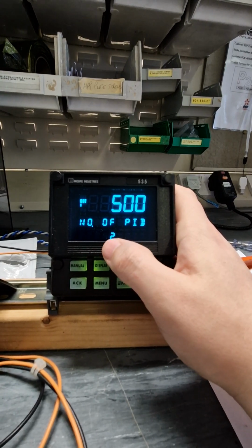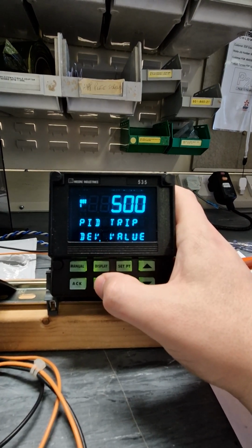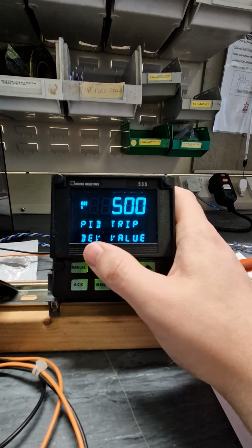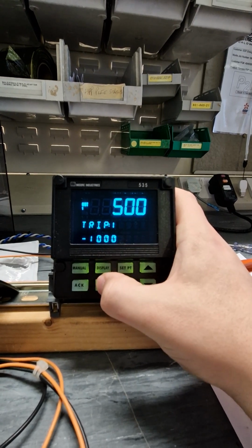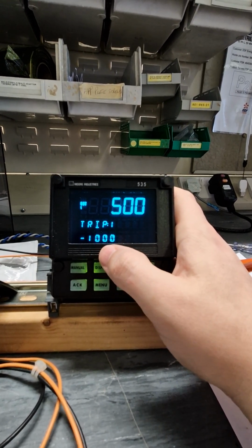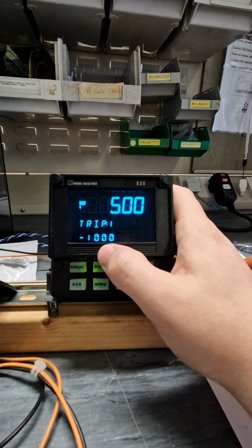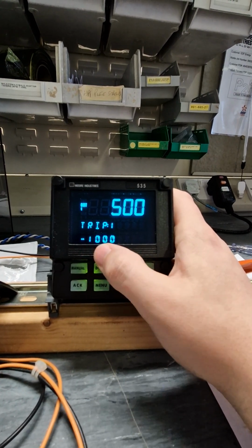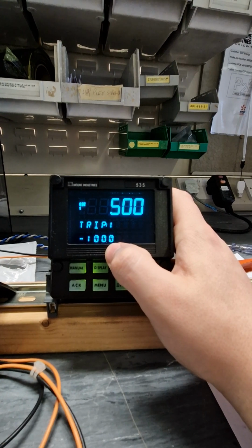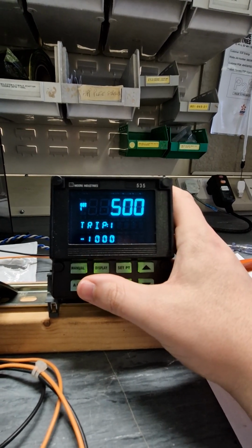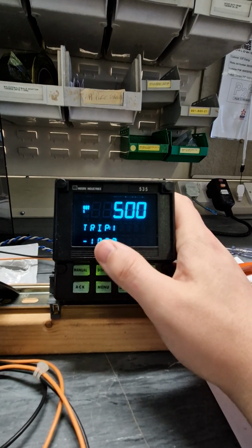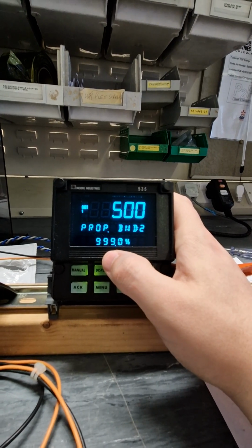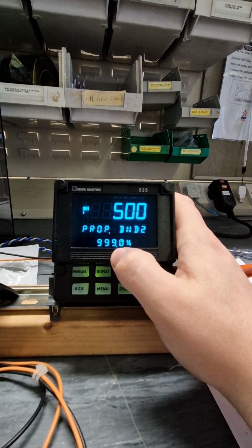Set the number of PID to 2, and the PID trip, so the reason it switches from 1 to 2 is the deviation value. And trip 1 must be set to a very low number for it to work, I found.